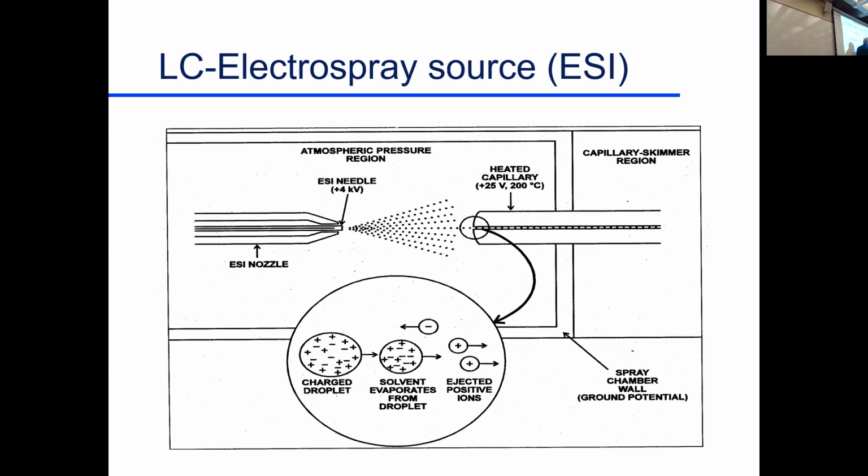And hopefully by the time you get into the point where it enters the mass spectrometer, you're left primarily with positive charges because you've got the ability to drag these positive charges out. So your negative charges really aren't attracted down this tube, only your positive charges. So negative charges, less solvent tends to be drawn out of this section to give you then just this concentrated beam of material from your LC column.